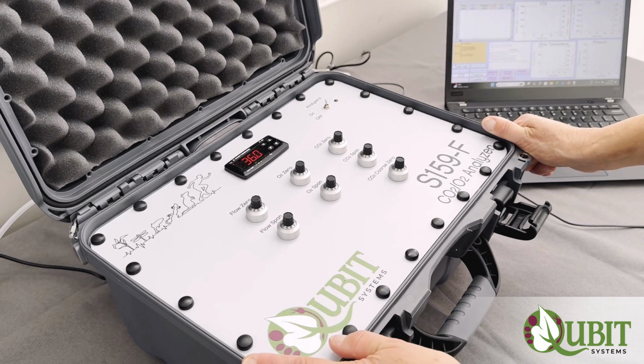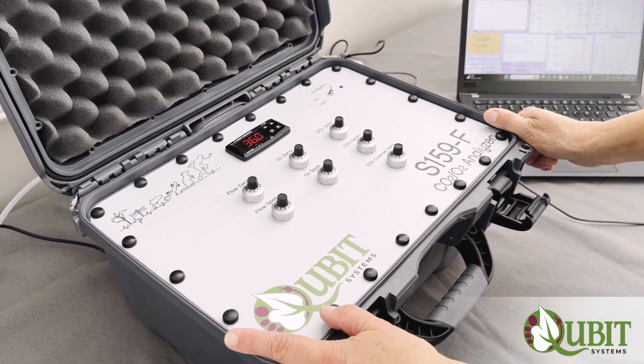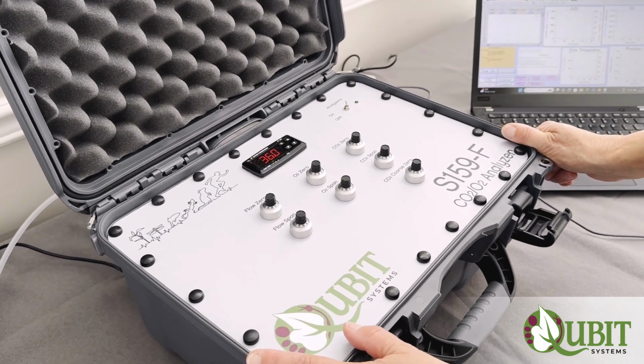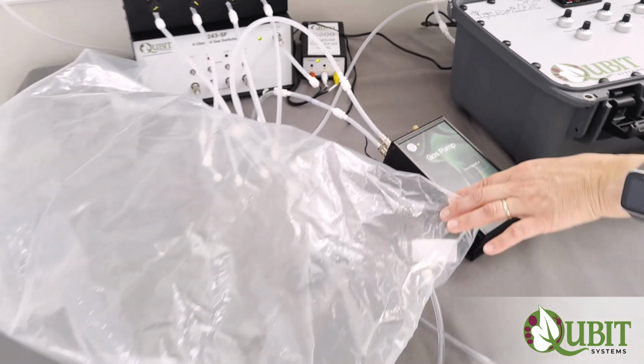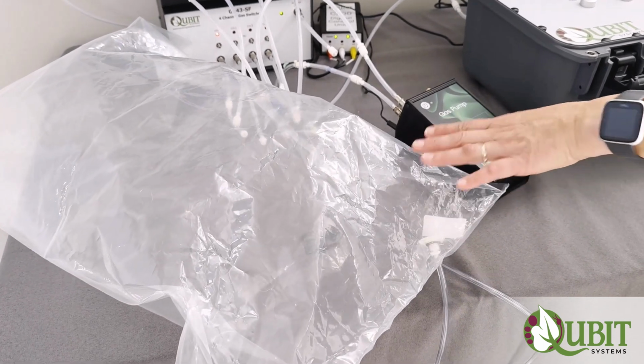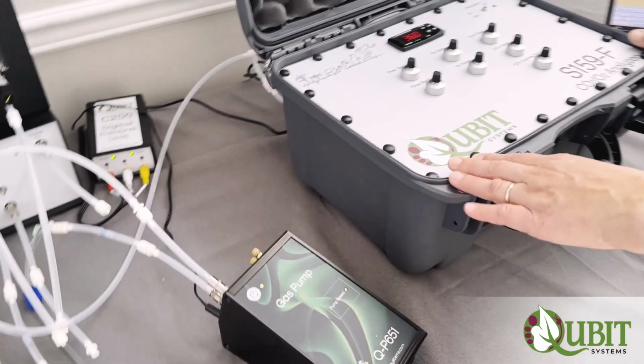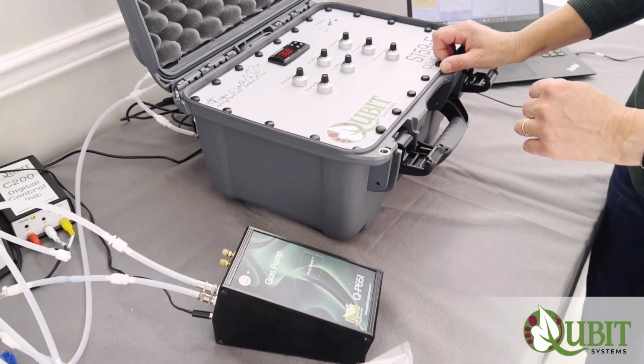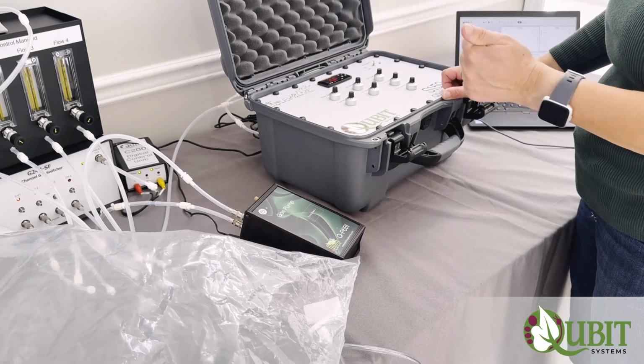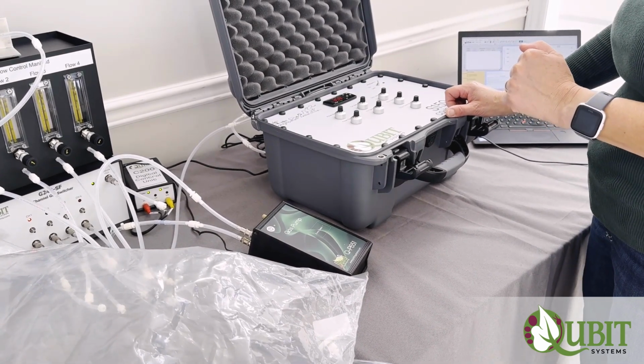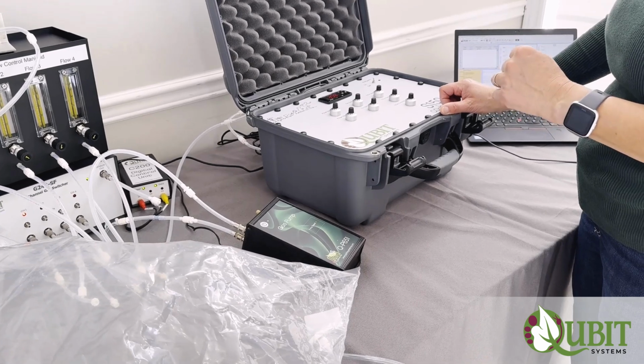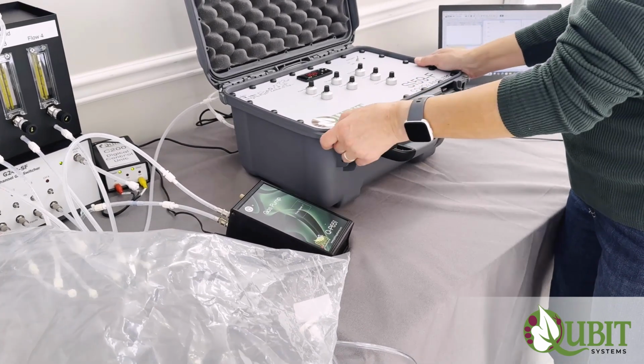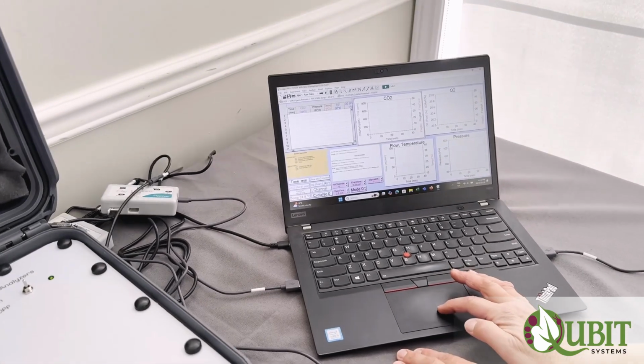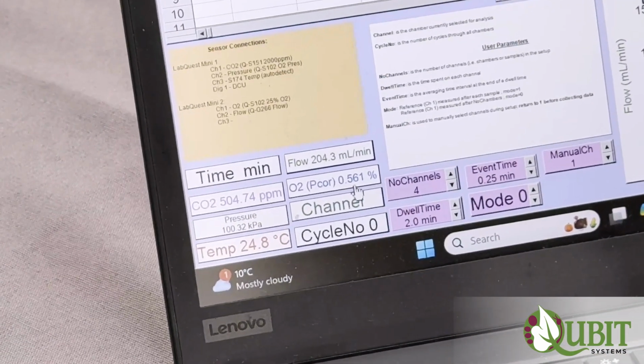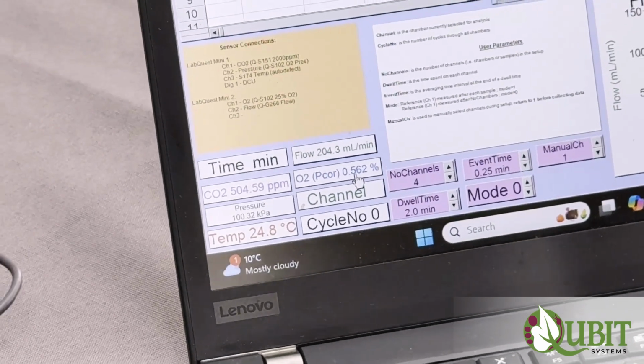For calibration of the oxygen sensor, again, we're using 2 points. It's a linear calibration. The first point has to be 0 oxygen, and that can come from a gas bag which has nitrogen gas in it, or in this case, I actually have the CO2 standard, which I used for calibrating the CO2 sensor, in a background of pure nitrogen. So with the same gas, 505 parts per million CO2 and 0% oxygen, I can calibrate both sensors. So we're putting a gas with 0 oxygen through the analyzer, and if you come up here, you can see that the reading under oxygen is 0.562%, so it's close to 0 but not quite.